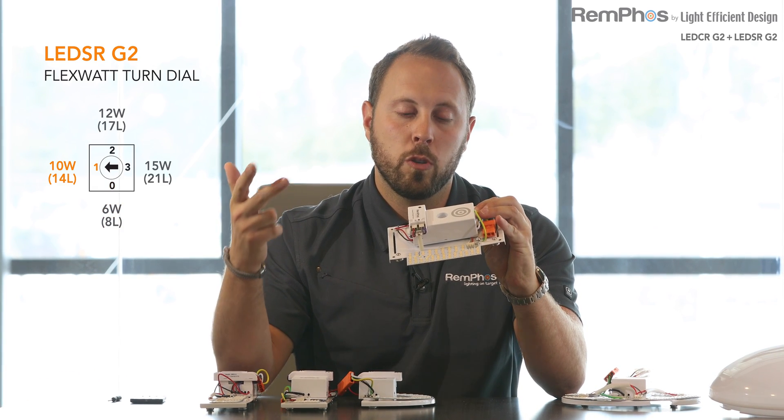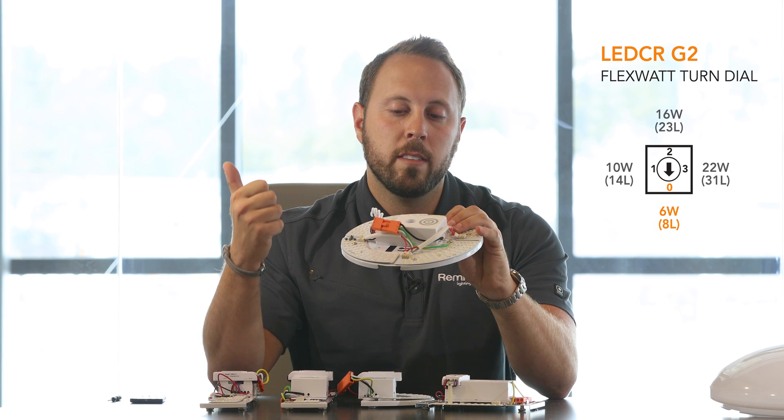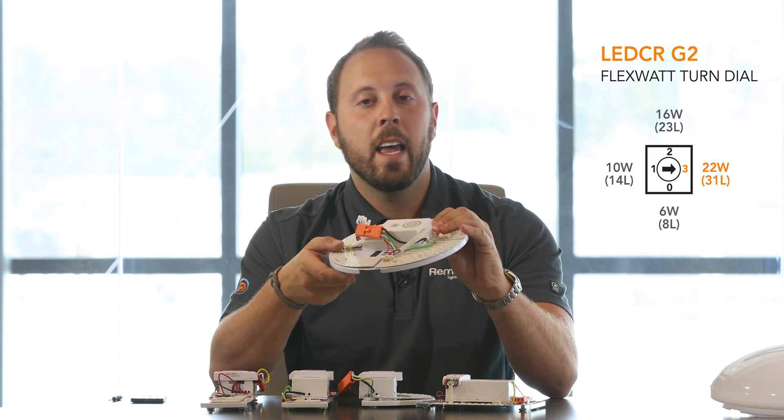At 130 to 150 lumens per watt, these retrofit kits have some of the highest efficiencies in their class, translating to super low wattages. On the LED SR kits, you can select between 6, 10, 12, or 15 watts. On the LED CR kits, you can select between 6, 10, 16, or 22 watts. At 6 watts, these kits provide over 800 lumens — enough to replace two 13-watt PL lamps, going from about 26 watts down to 6. On the high end, two circline lamps using 60 to 70 watts can be brought down to 22 watts.